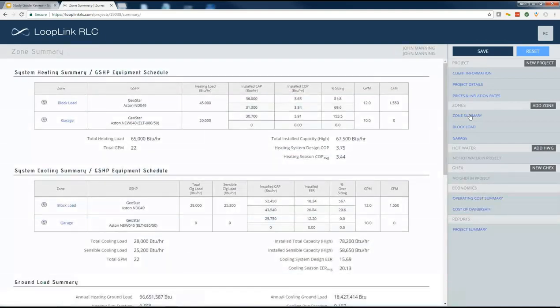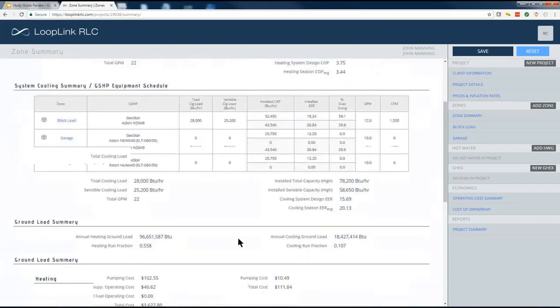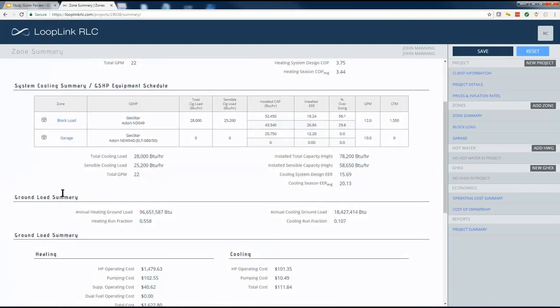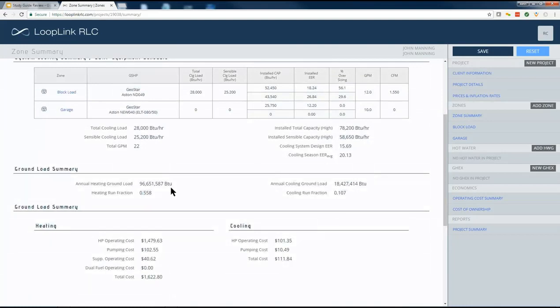Now if you go to the zone summary, you can see we've got our 4-ton unit forced air, 3.5-ton unit water-to-water. You can see combined heating loads. You can see combined installed COPs and average COPs, combined flow rates. The other thing that you can see are your combined operating costs on the bottom of the page. And you can see your combined heating ground load versus your cooling ground load. So this is the amount of energy that we take out of the ground loop in the winter heating season.